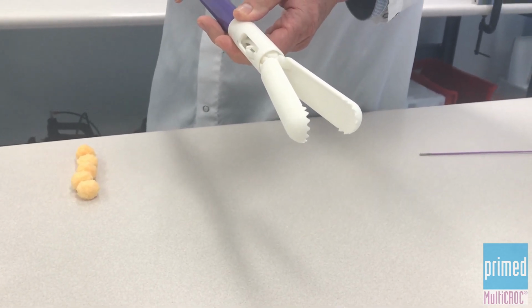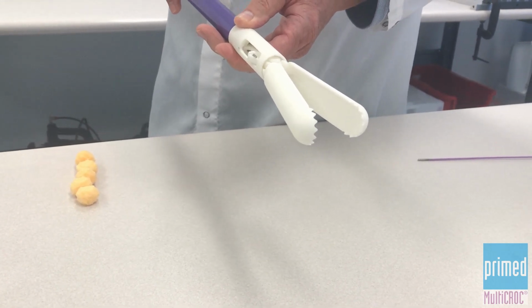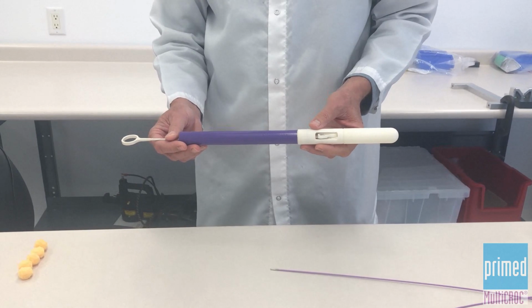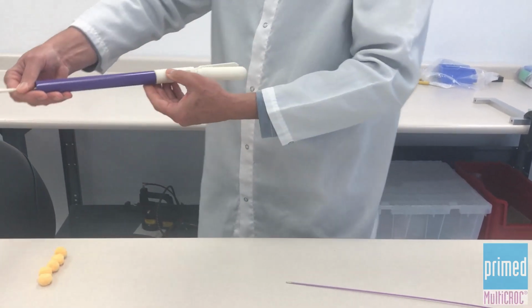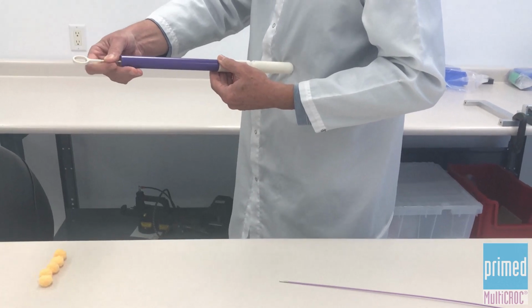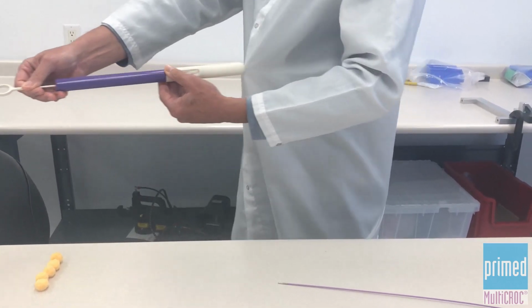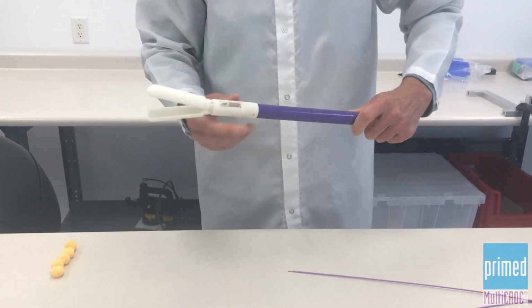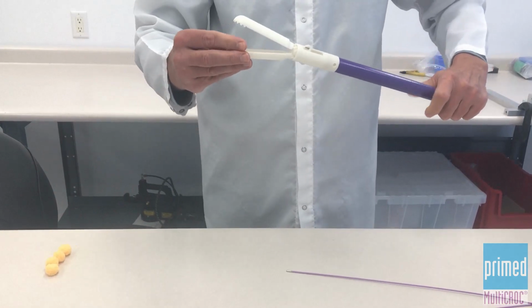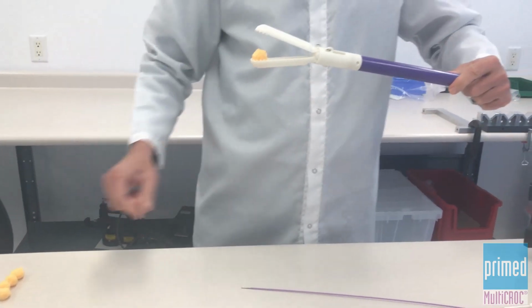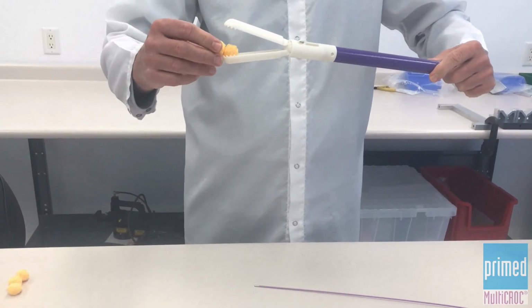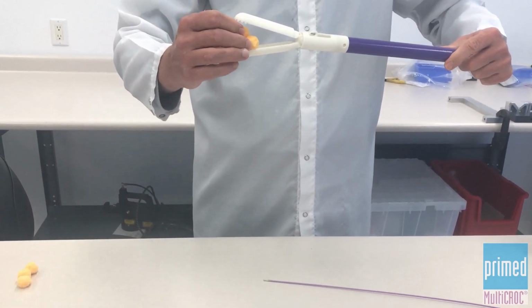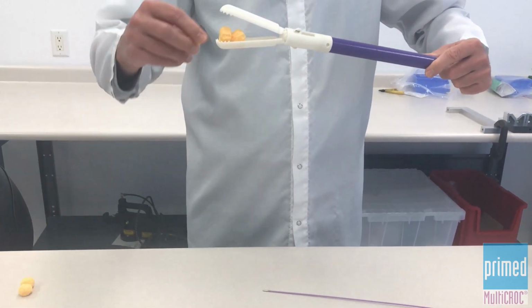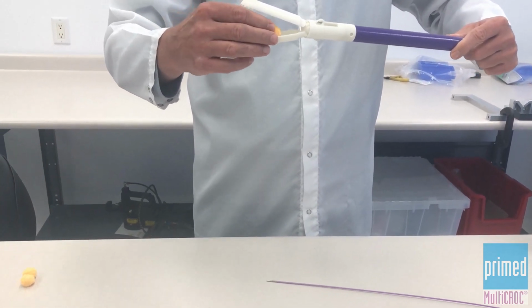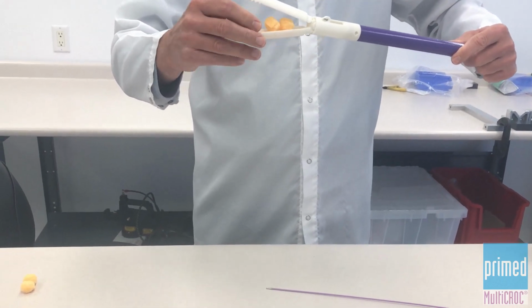Let me explain the multi-sampling feature of the MultiCROC and how it works. In order to take the biopsies, open the device, approach the site as you would normally do with the standard biopsy forceps, close and pull. The first sample is stored in between the jaws of the MultiCROC. We repeat the cycle, and the second tissue sample pushes the first one in. The third pushes those two back until the jaws are fully loaded with the specimen.